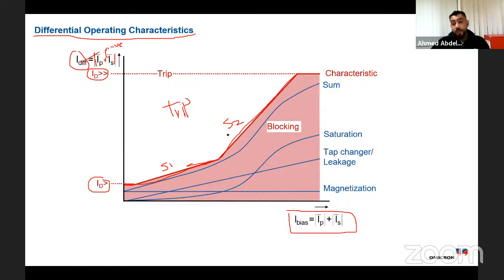The values of S1 and S2 depend on your system calculation, because you need to go back to the nameplate of your transformer and understand the magnetization current. If you remember from the equivalent electrical circuit, the magnetizing current is a current passing through the iron core but not leaving. So it is a normal differential current, and you should put it in your calculation. So the magnetization current, which is IM, flows in the XM. So this is a normal error.